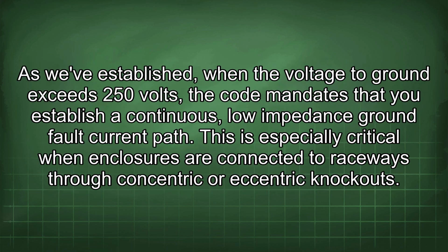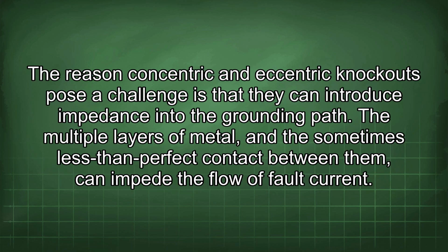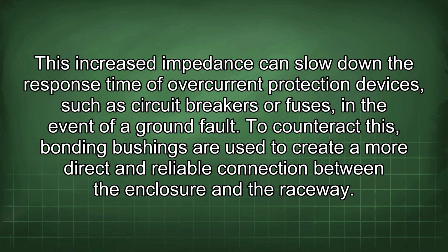As we've established, when the voltage to ground exceeds 250 volts, the code mandates that you establish a continuous, low-impedance ground fault current path. This is especially critical when enclosures are connected to raceways through concentric or eccentric knockouts. The reason concentric and eccentric knockouts pose a challenge is that they can introduce impedance into the grounding path. The multiple layers of metal and the sometimes less than perfect contact between them can impede the flow of fault current. This increased impedance can slow down the response time of overcurrent protection devices, such as circuit breakers or fuses, in the event of a ground fault.